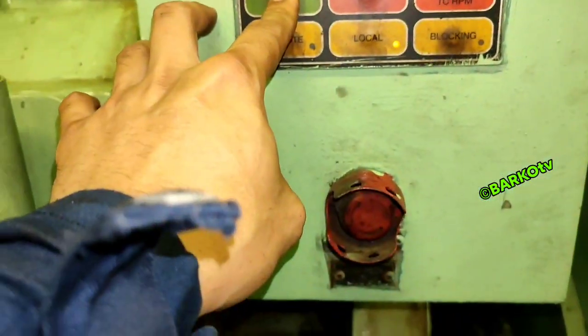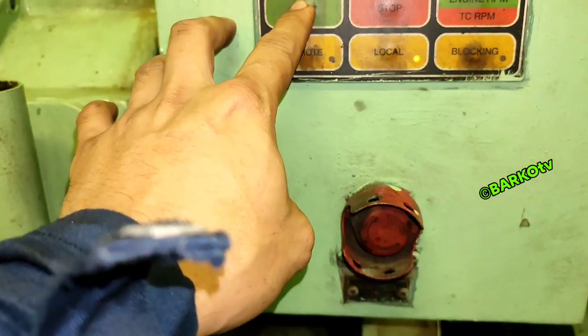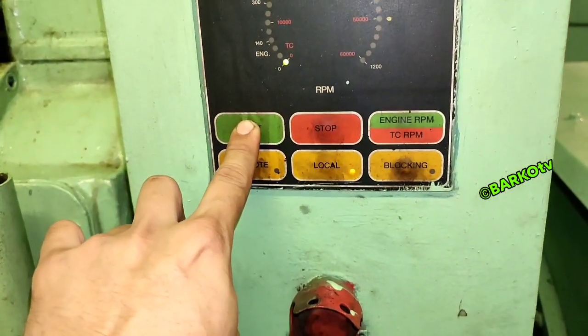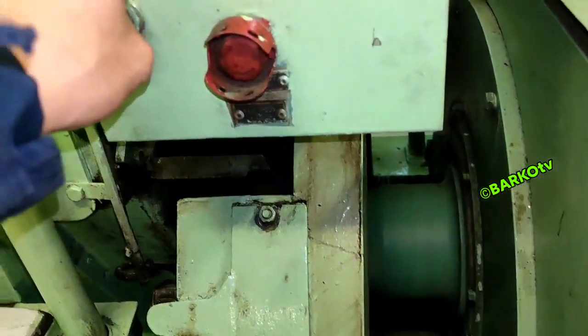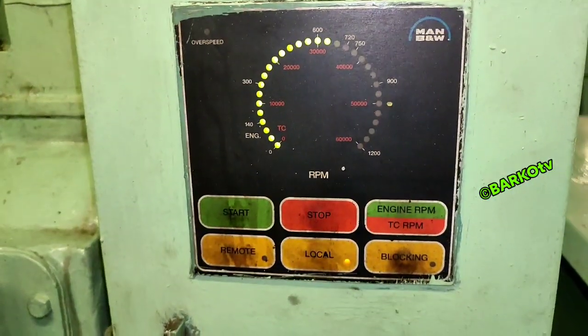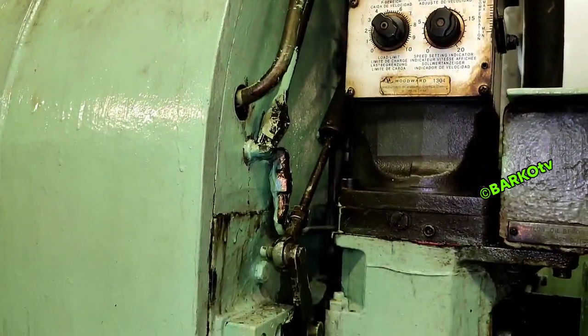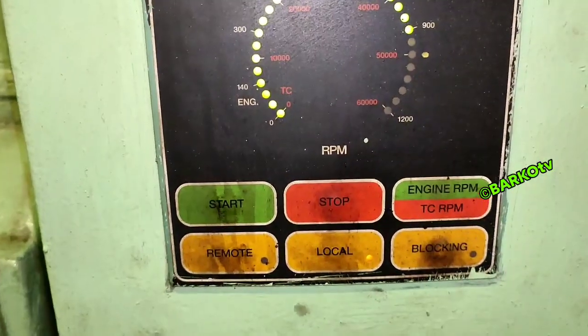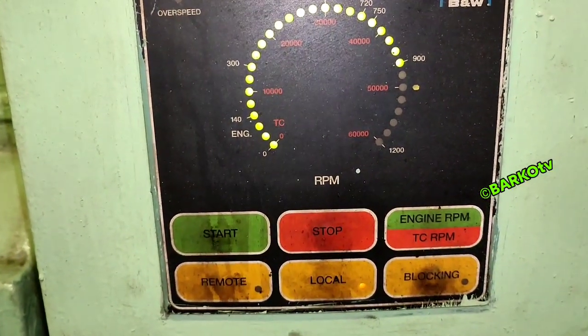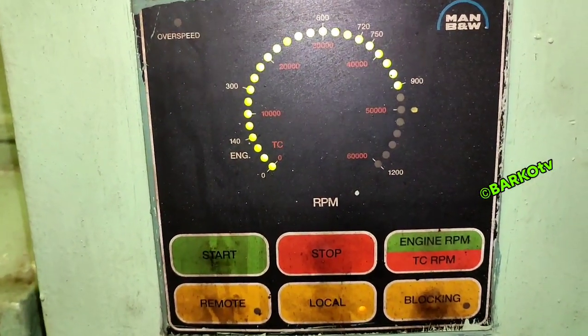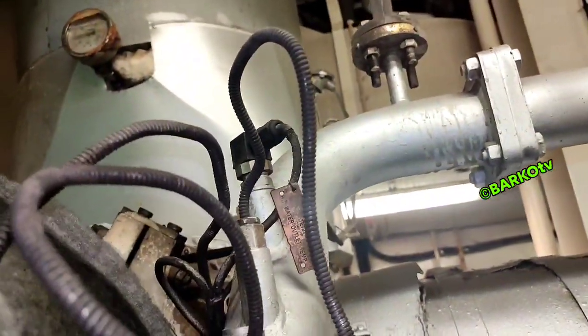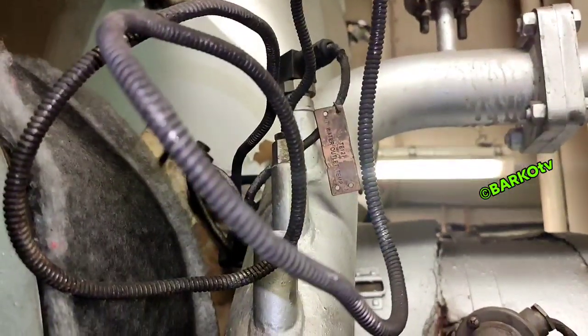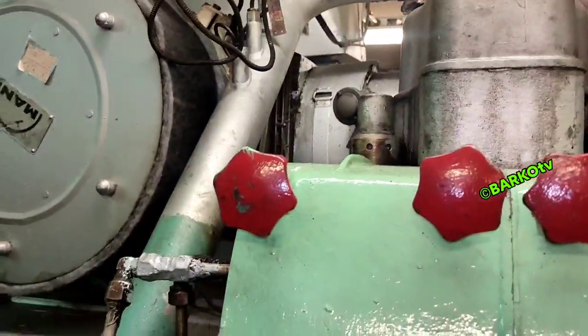Next, after that, start again. Then we do the HT fresh water temperature, high temp at 95 degrees. Here we only simulate electrically. We do it at the temperature switch, but also, if the inspector wants actual, you need a temperature calibrator set to 95, and then the calibrator must activate this sensing point for our HT temperature switch.